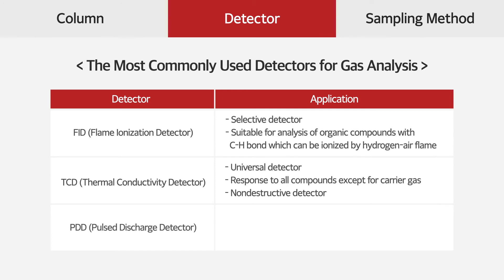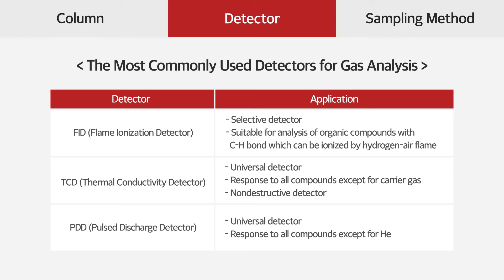PDD, as a universal detector, can detect all compounds at trace level except for helium, the carrier gas, so it uses for trace level gas analysis.